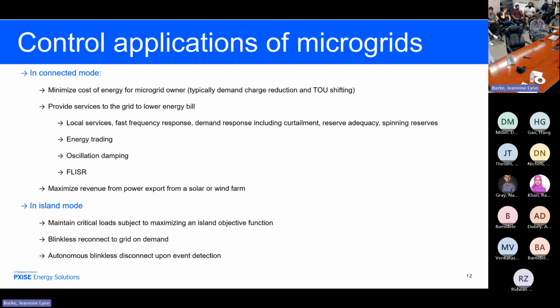There are two other applications. One is oscillation damping. If the control system is able to respond fast, by control system I mean the microgrid itself, the microgrid set point. If I'm able to give the microgrid set point a change of P and Q simultaneously, I can then dampen the oscillations of the grid. And as you learned in your Control 101 class, you can calculate what the tuning coefficients are to cut off all frequencies lower than that number. That's how we tune the controller as an oscillation damper.